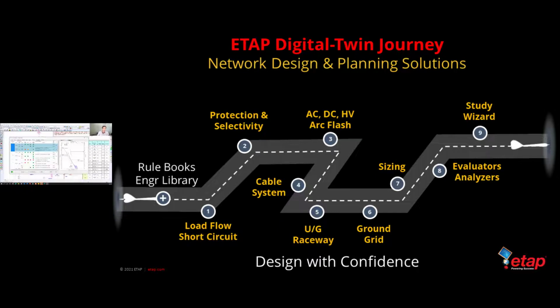And it tells you on the primary side, we have a protection pickup limit as well. Full load amp is done well. Inrush is good and damage curve is good. On the secondary side, the pickup limit is not done well. And it doesn't just flag it, it tells you exactly why. So here I have a long time pickup of 390 amps, which is below the minimum limit of 420, which comes from base FLA times 100%.